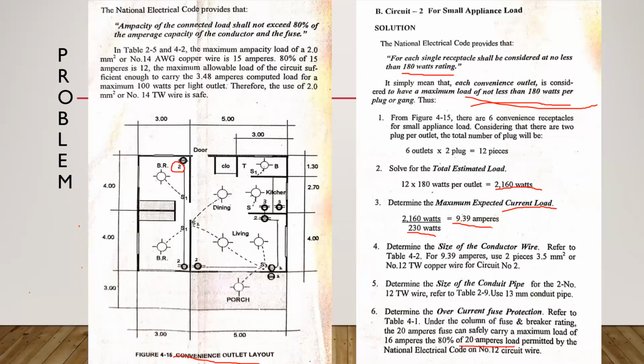No, kahit na, di ba, sabi doon din again sa ating guidelines na 80% lang ng ating fuse ang gagamitin. So yung 80% niya is 16 amperes. So maximum pa rin siya or malaki pa rin siya kaysa dun sa ating na-compute. Pero dahil na-specify sa NEC, yun pa rin ating gagamitin, 20 amperes.